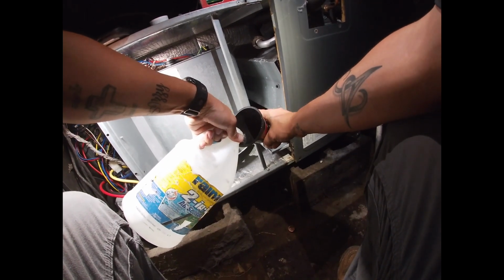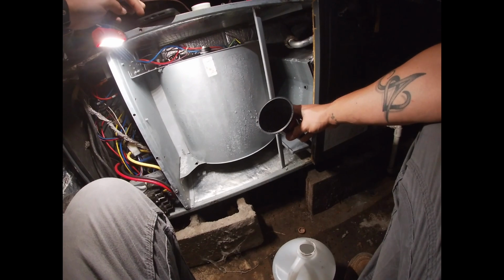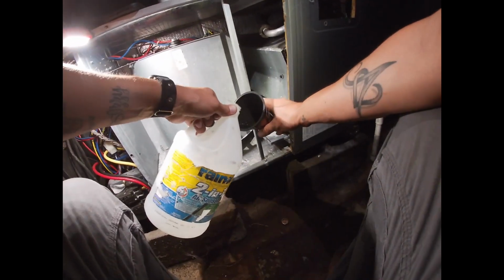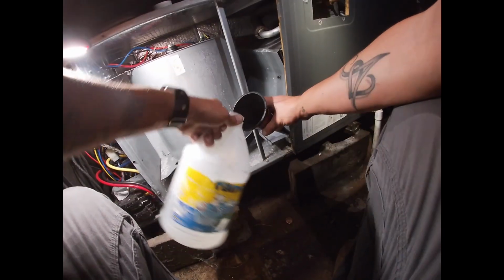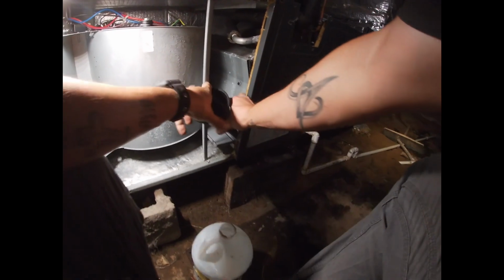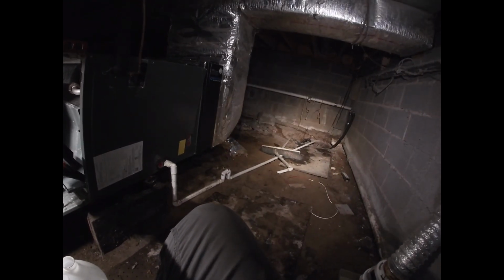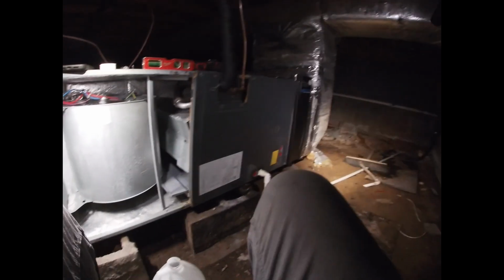Trap at all. All right, well, got that taken care of. I'll have to go pick that heater kit up. But the drain was stopped up. I'm getting water out of it now. You guys probably can't see that on the camera. It is draining steadily. So we got that problem taken care of.